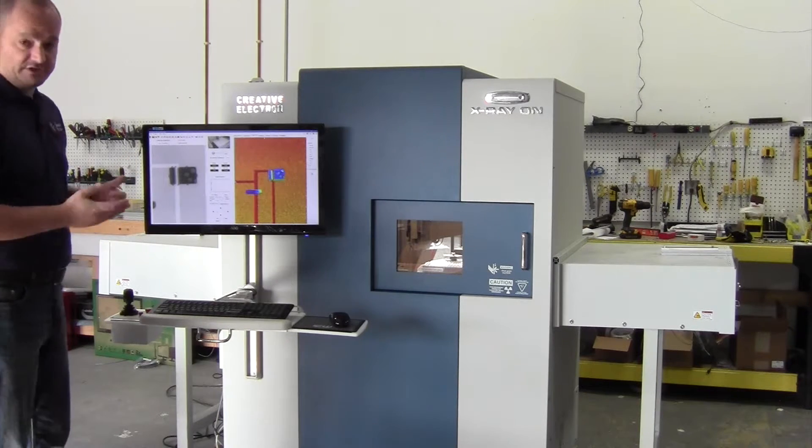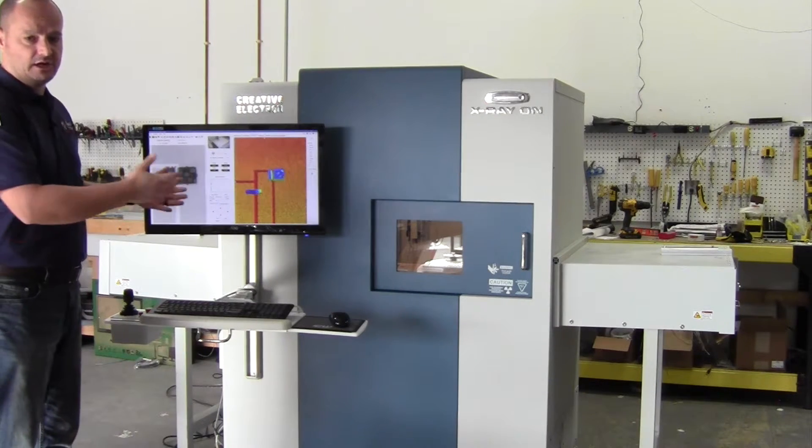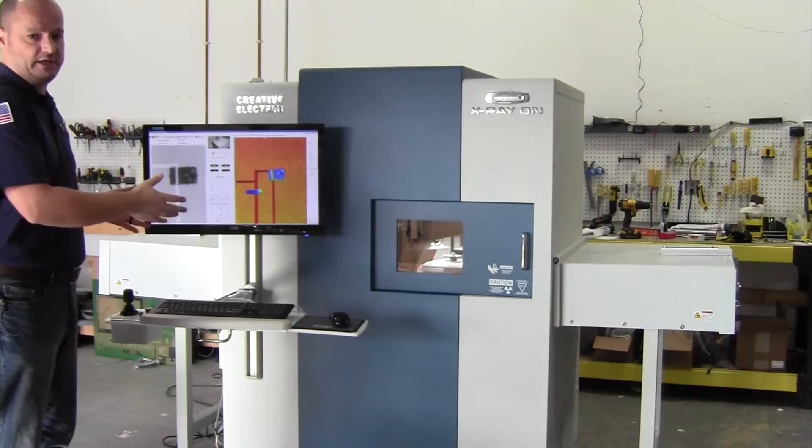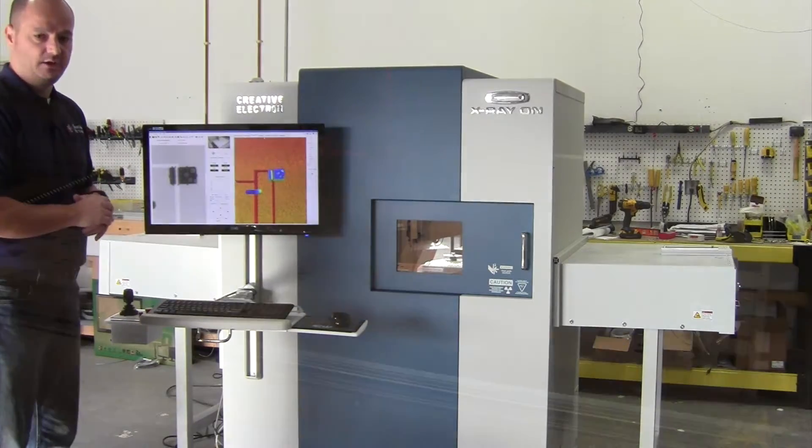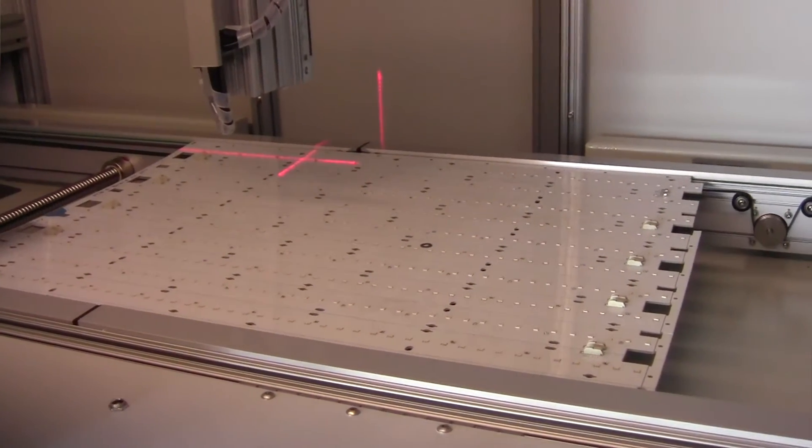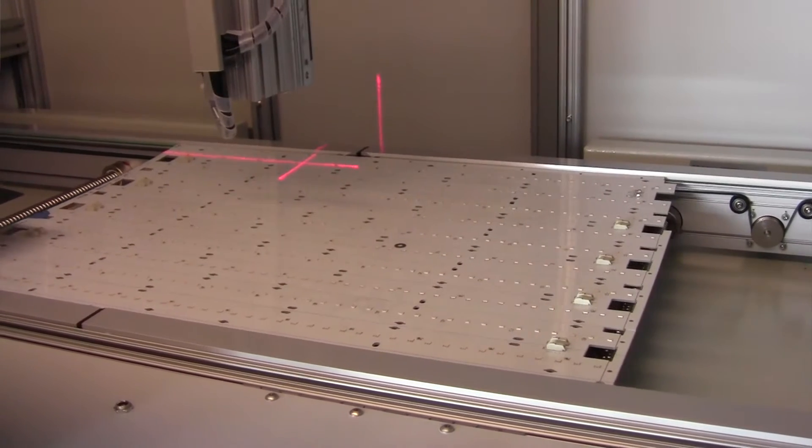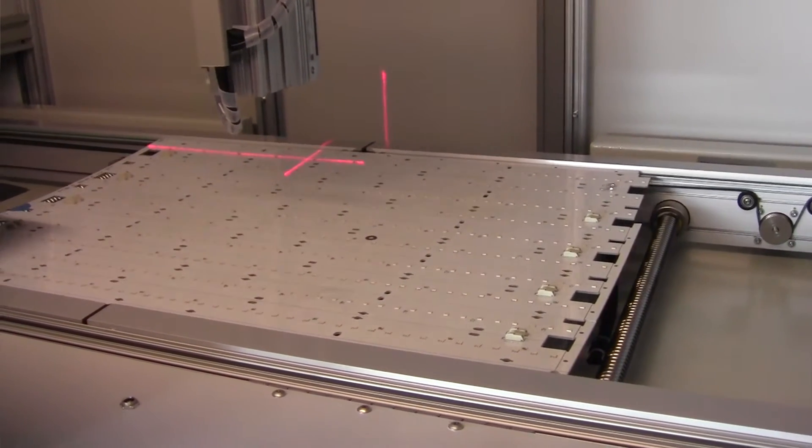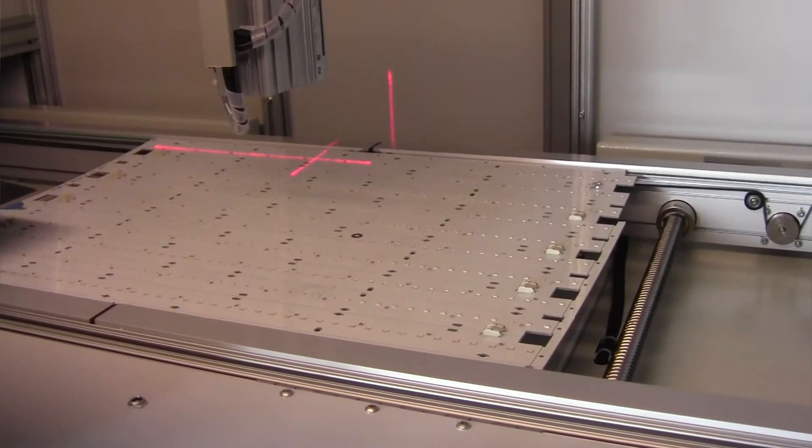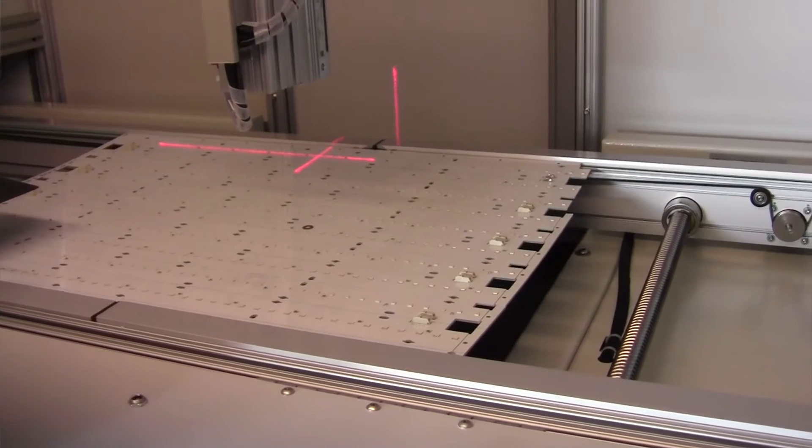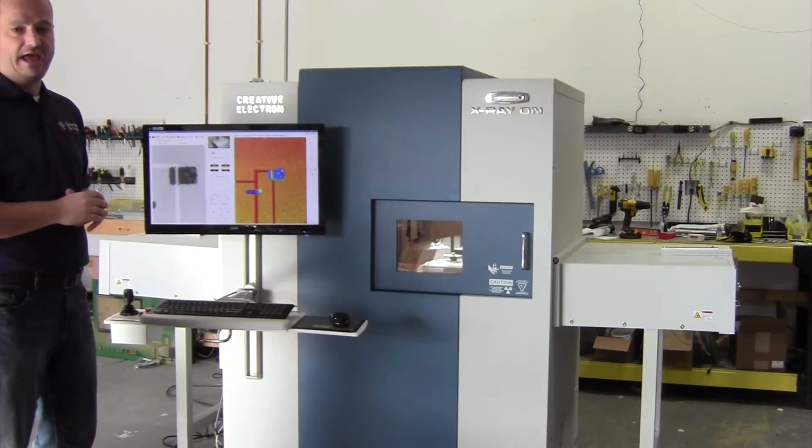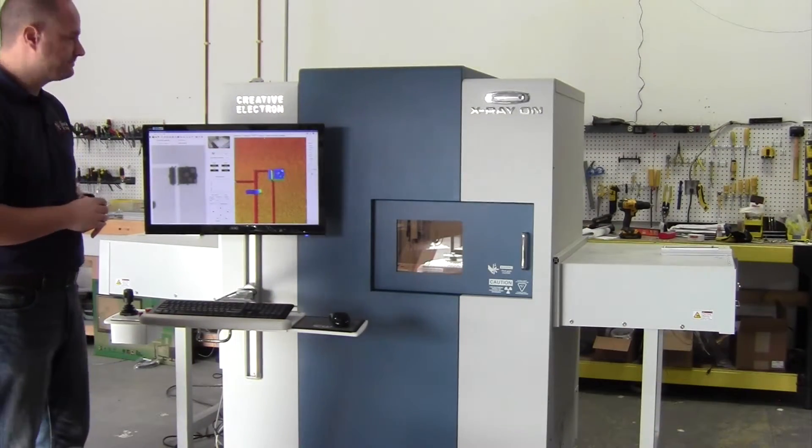For example, in this case we're looking at a large 20 by 48 inch panel with LEDs and we're looking to measure how much void each one of the LEDs has. After that, you can do statistical analysis and understand any issues that you might be having with your process.